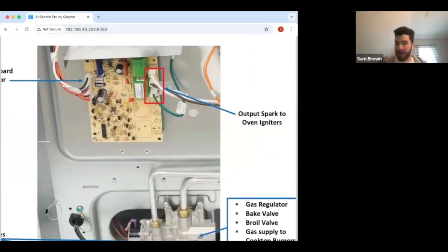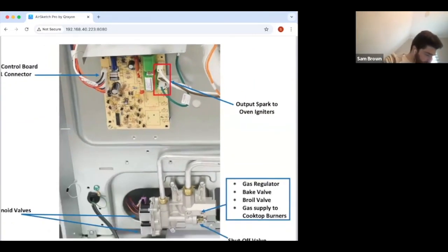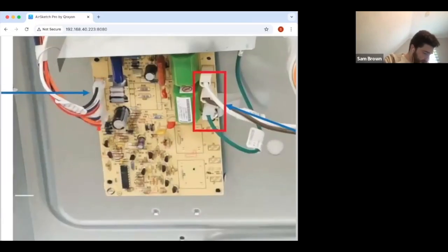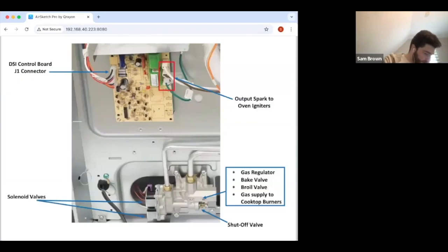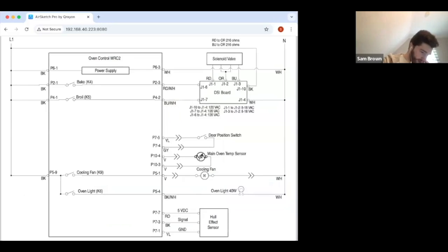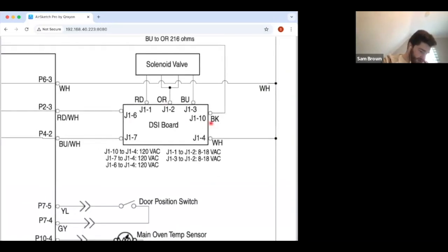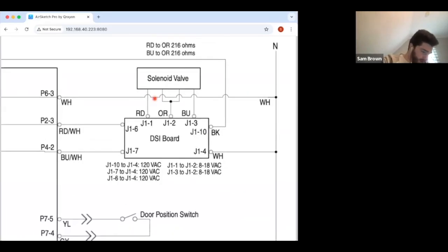We'll get into why that ground is so important to the flame sensing in a second. This connector here is where you have all of your low voltage stuff going on, all of these pins. I say low voltage relatively, lower than the spark voltage. Your normal 120, or for the solenoid valve, it's actually a low DC voltage.